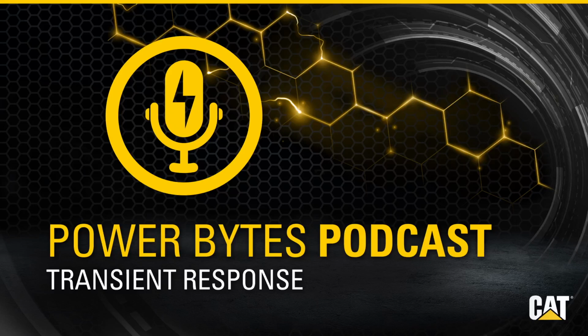Also, we would recommend a lower subtransient reactance on the generator. This allows the generator, again, to respond faster to loads like motors or transformer inrush. Finally, if you already have a generator on site that you need to improve the transient response, there are some changes that can be made to the voltage regulator that may improve the response.